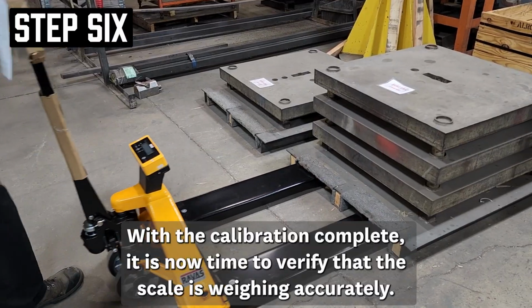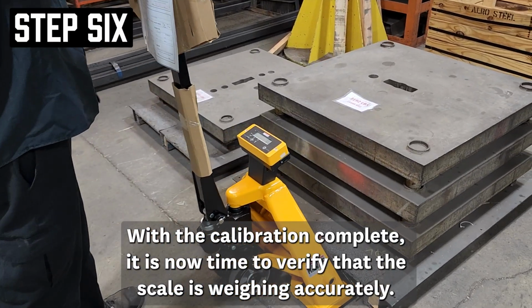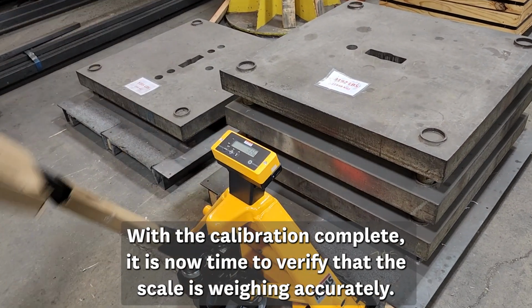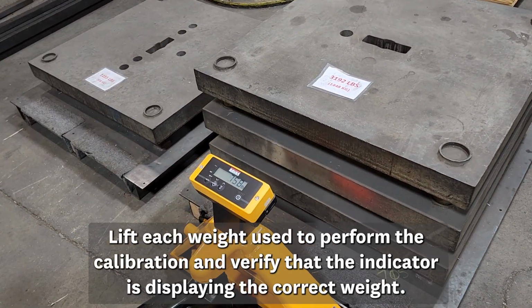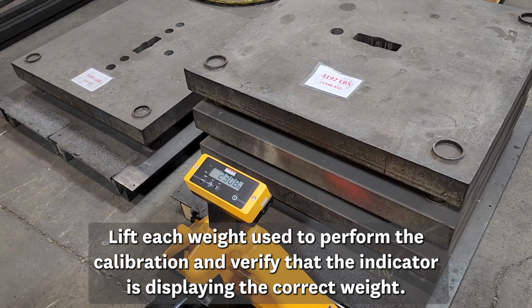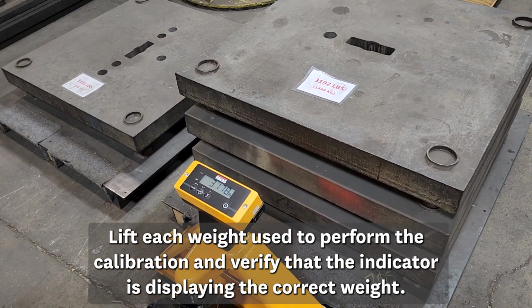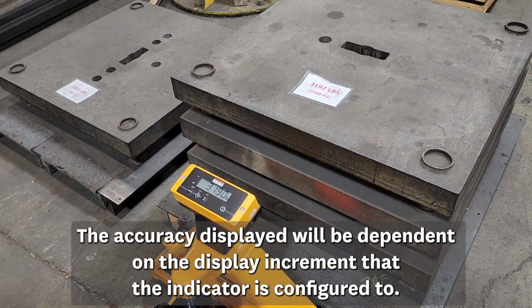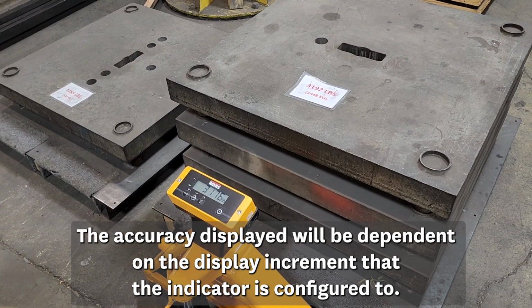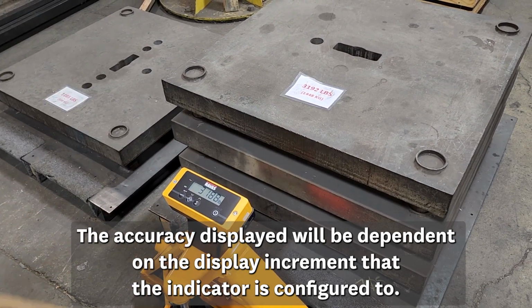Step 6. With the calibration complete, it is now time to verify that the scale is weighing accurately. Lift each weight used to perform the calibration and verify that the indicator is displaying the correct weight. The accuracy displayed will be dependent on the display increment that the indicator is configured to.